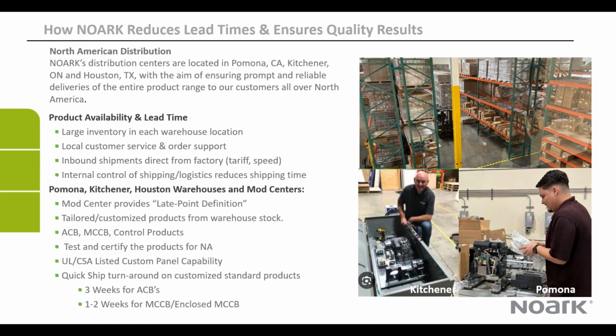Okay, and then the last point here about our warehouses is we've implemented what we call mod centers. So the photo in the bottom right-hand corner is our air circuit breaker mod center in action in the Pomona warehouse. And we call this late point definition. So we bring in breaker frames that are substantially completed, and then in the mod center, we add the trip units and accessories that turn them into the exact model that a customer would require.